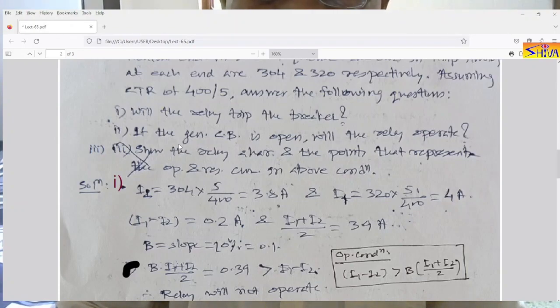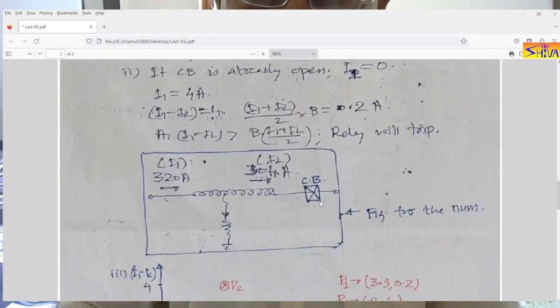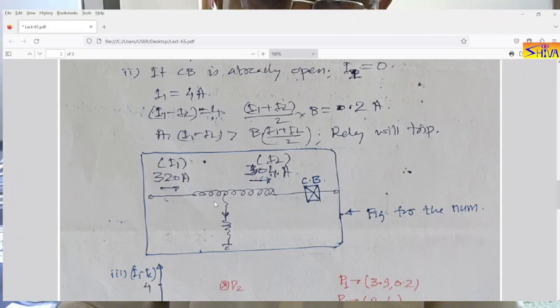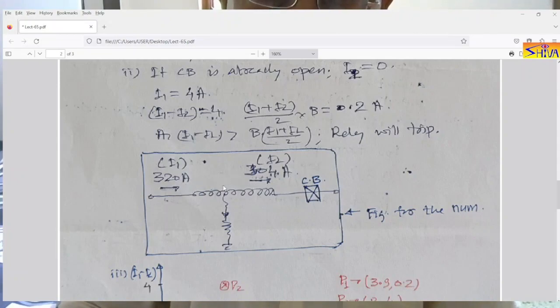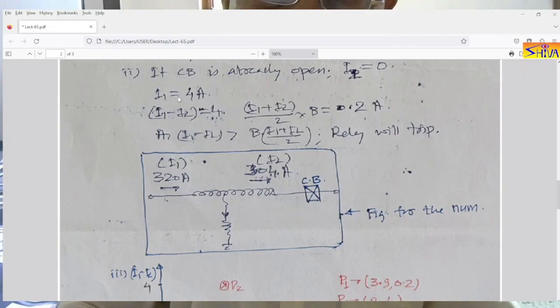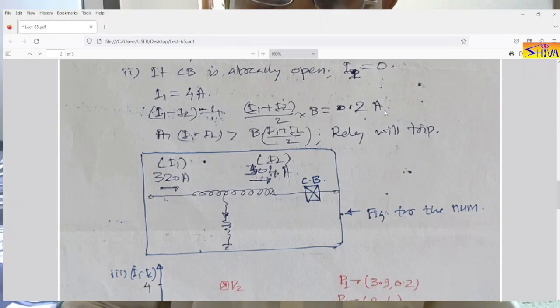Now the second part: if the generator circuit breaker is open, will the relay operate? If the circuit breaker is open, I2 becomes 0; only I1 remains. So I1 (from the CT secondary) is 4 amperes and I2 is 0. Then I1 − I2 = 4, and B × (I1 + I2) / 2 = 0.1 × (4 + 0) / 2 = 0.2. Since 4 is greater than 0.2, the condition IS satisfied. Therefore the relay will trip.